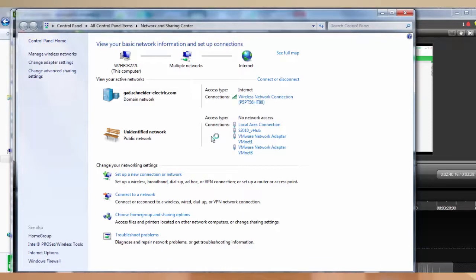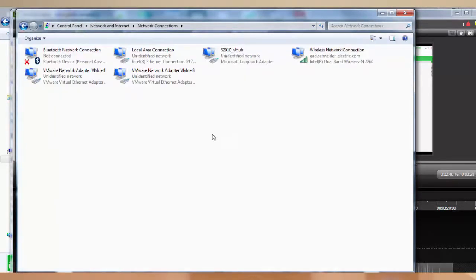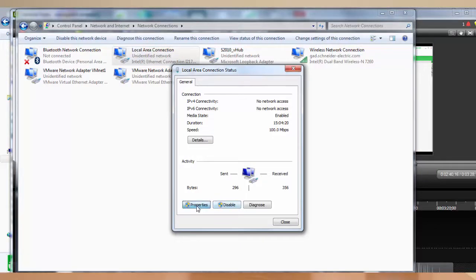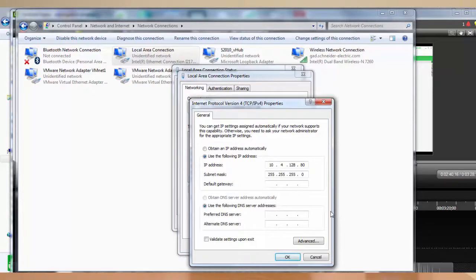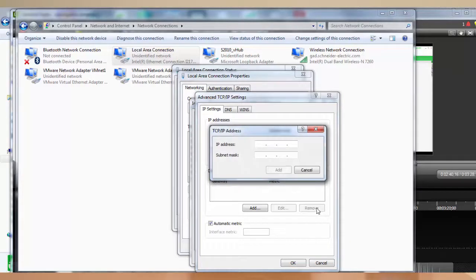In order to add an IP address range to your PC adapter, you can use the Control Panel. After that, select 'Change Adapter Settings', select your local area connection, double click on it, change properties, and select the IPv4 standard. After that, click Properties — you will have a fixed or dynamic IP address here, but if you click the Advanced button you can add the same IP address range you have in the relay, but select the host IP to be a different number.